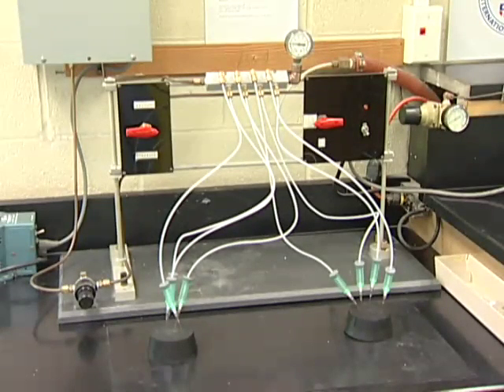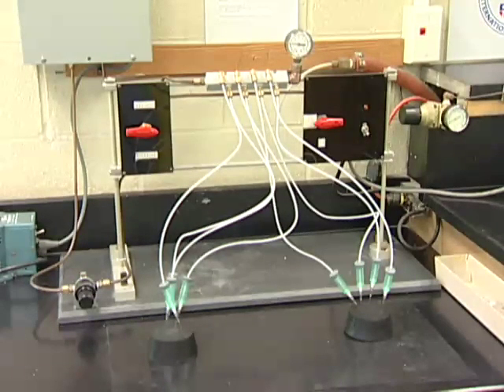This type of system is also plumbed to a vacuum pump. The gas and vacuum pump are both attached to a three-way valve that leads to a manifold with attached gassing lines. This allows the same gassing line to be used to add gas or evacuate gas.